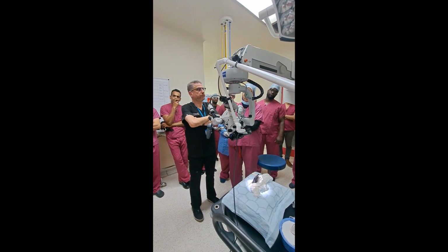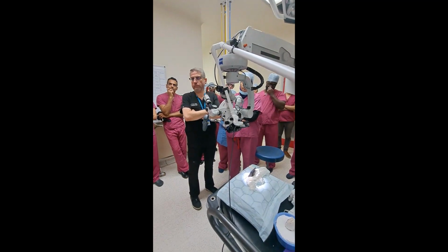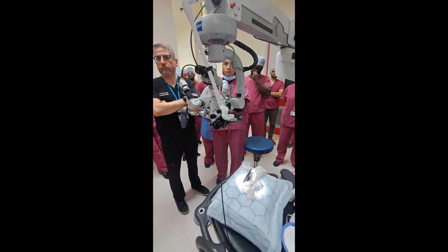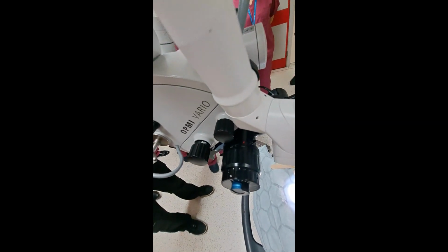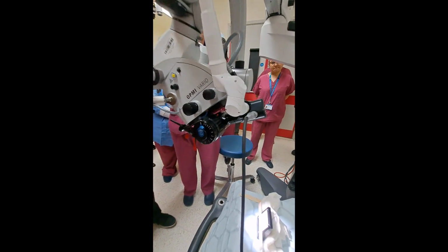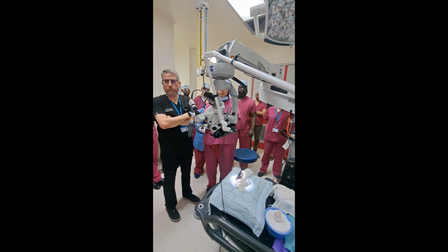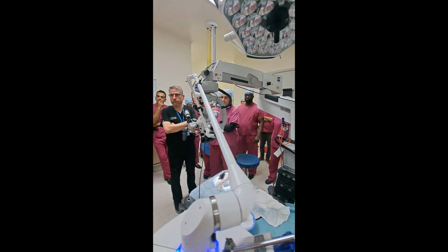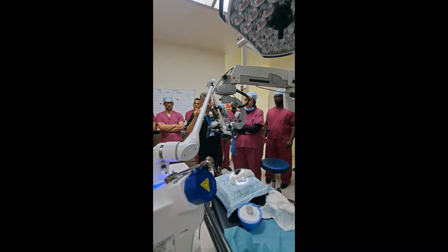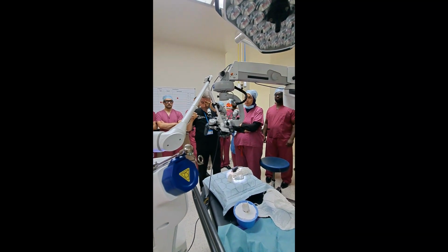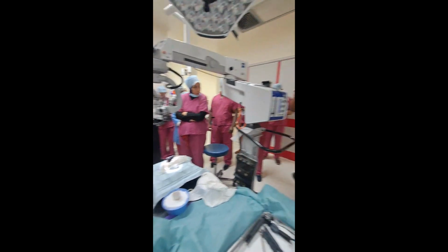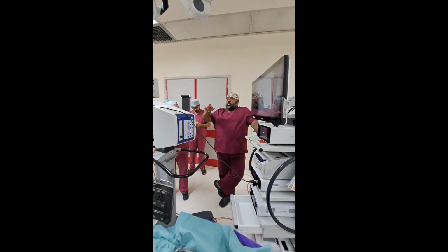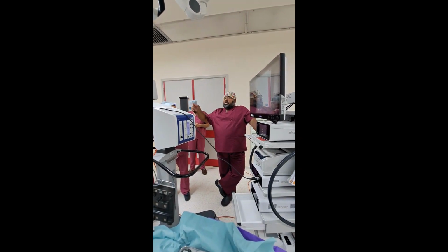I always think the simplest way of doing it is to set a baseline and then bring the microscope in, because that is the principle at which the laser will cut properly. It is focused to 400. And if the laser isn't cutting properly, it will be a focusing issue. It will all be premised on the distance. So that's really important, because you've got multiple variables, and if you change one and miss changing the other, then you end up with that problem.